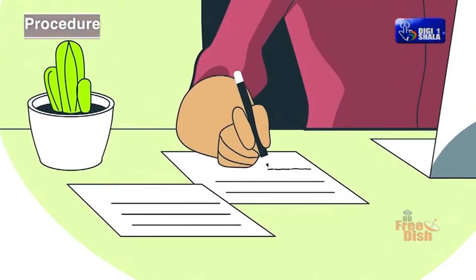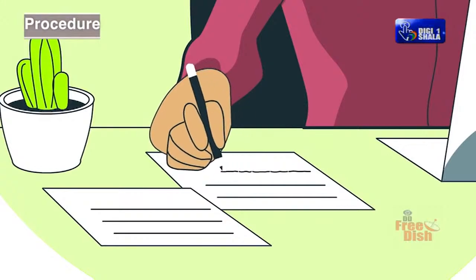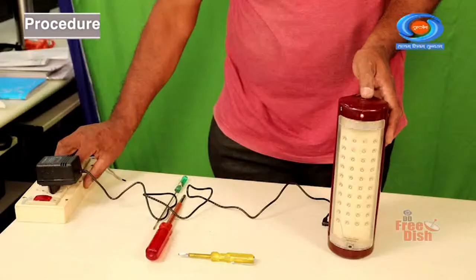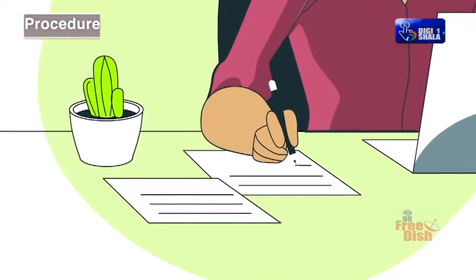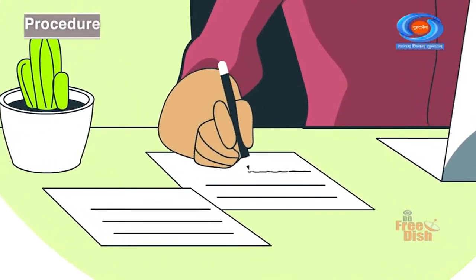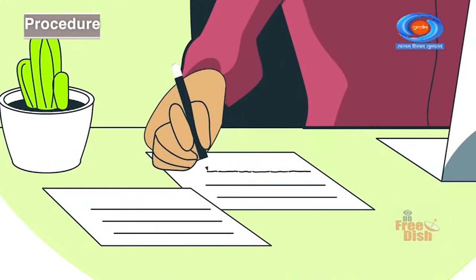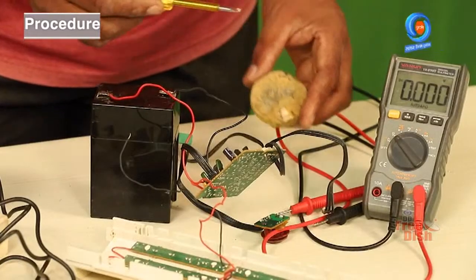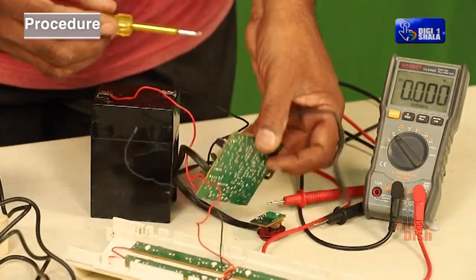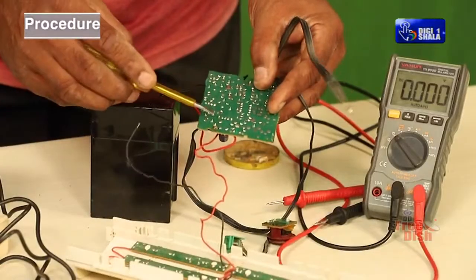Analyze the status of the circuit by the meter's reading. If the emergency light is without short circuit fault, connect it to the supply mains and switch on. Check the symptoms of the unit and record the symptoms. If you find any issues, repair or replace the wiring as necessary.